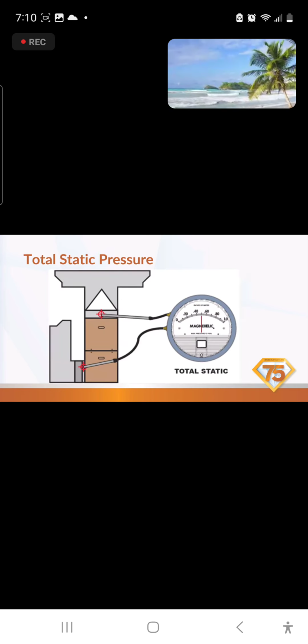When we say check your static pressure, what we want is your total static pressure, which is across the blower pretty much. I want to check on the furnace before the coil and without the filter in. So you're kind of between the filter and the furnace and between the coil and the furnace on a gas furnace. We just want the static pressure across the blower.